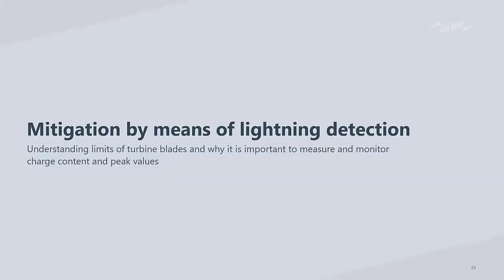Now, once we've done a risk assessment and we know that our turbine will get struck 67 or 68 times per annum, it's very important for us to mitigate that risk as much as possible to ensure that we avoid unplanned maintenance and unplanned downtime. We know also now that it's not possible to avoid lightning strikes to a turbine. We know that the majority of lightning strikes would be upward lightning, and that we've done our risk assessment and we know what to expect. How many times per annum will my turbine be struck?